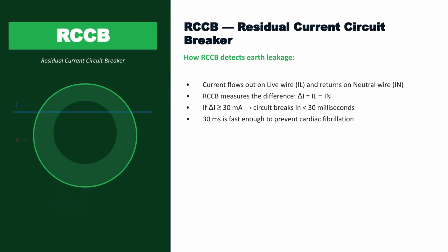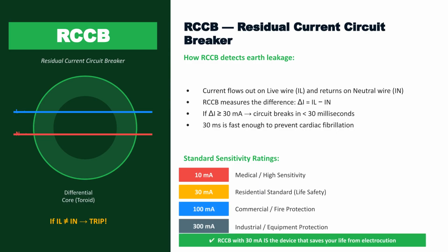The RCCB is the life-saving device. It measures the difference between the current flowing out and the current returning. If the difference, the residual current, reaches 30 milliamps, it trips in less than 30 milliseconds. This speed prevents cardiac fibrillation. The 30 milliamperes RCCB is the residential standard for life safety.